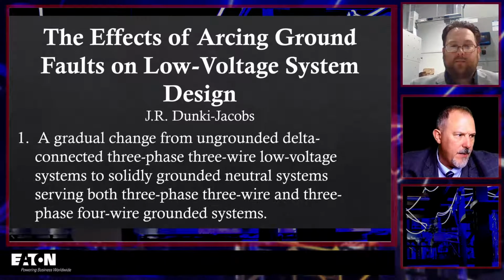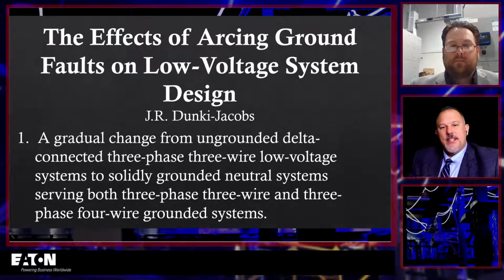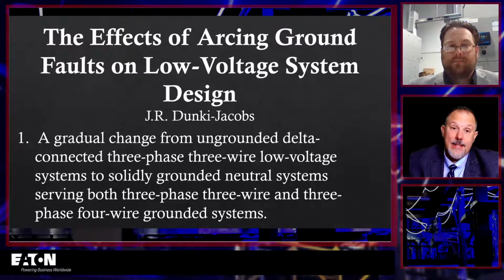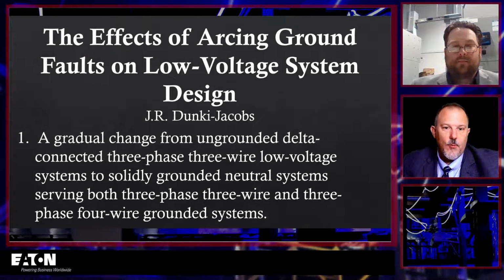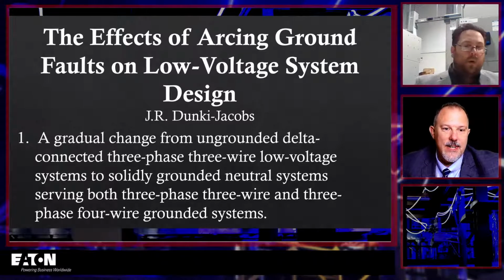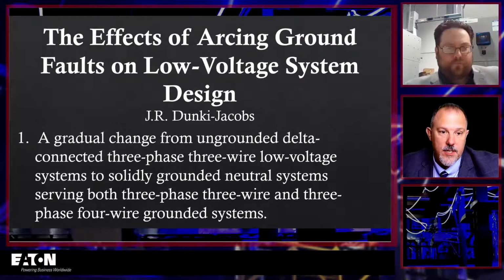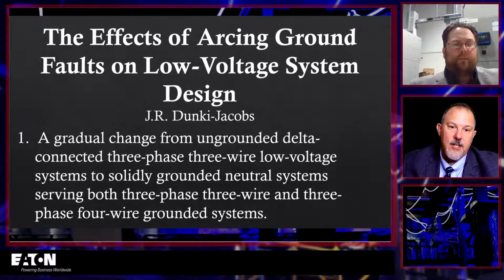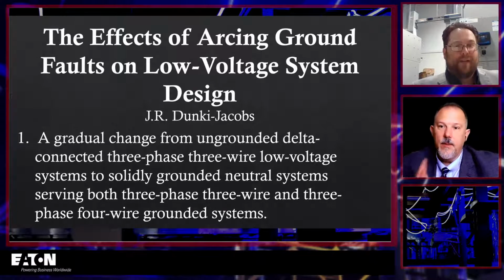I think it was this paper. Yes. So what he did say was that we had a gradual change from ungrounded delta connected three-phase, three-wire low voltage systems to solidly grounded neutral systems serving both three-phase, three-wire, and three-phase, four-wire grounded systems.